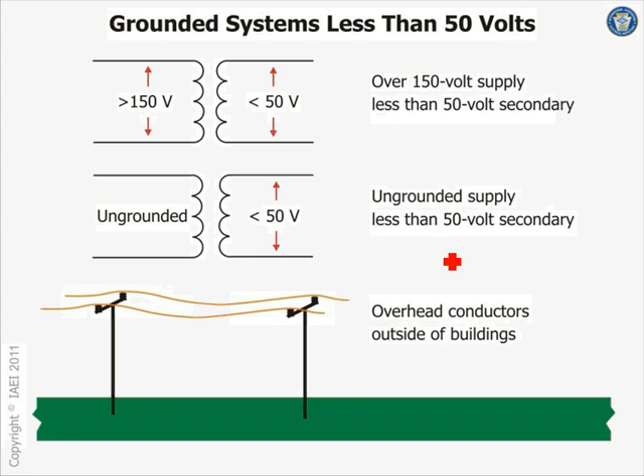But there are exceptions. One of the exceptions: the control circuit is controlling very important equipment here, and if a ground fault will interrupt the control circuit and create more hazard, then you don't need to ground this control circuit. Ungrounded supply: so if you decided to take a 480 here to a control circuit, these are all control circuits, class 2 and class 3 circuits, and the voltage is 24 or 12 volt here, and you're feeding it from 480 ungrounded, you are to ground the secondary here. The secondary, not the primary. Again, there's an exception for creating more hazard.